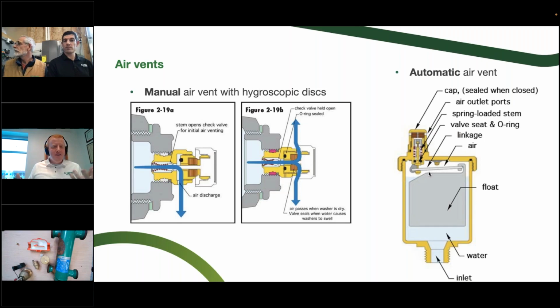And what's going to happen at that point is you're going to remove whatever air pocket is inside that air vent, which is great because then water will come out. You'll know that it's full of water, but the problem is that by removing that air pocket, any floating debris on top of that water line is now going to be in your valve, your needle valve that keeps that air vent from leaking all over the place. And obviously that's what we don't want. We want to make sure that air vent's not leaking, but definitely don't push down on that needle valve in the top. And then we show a little bit on this slide here, plan B.